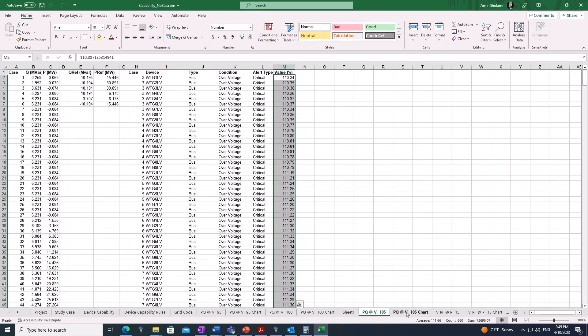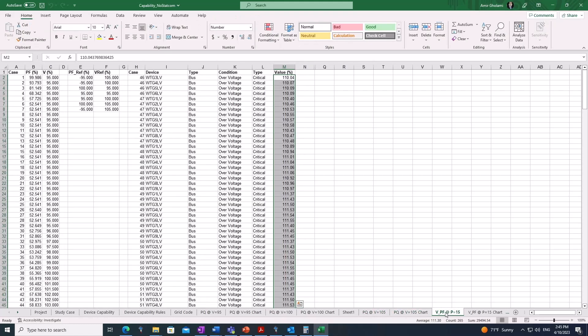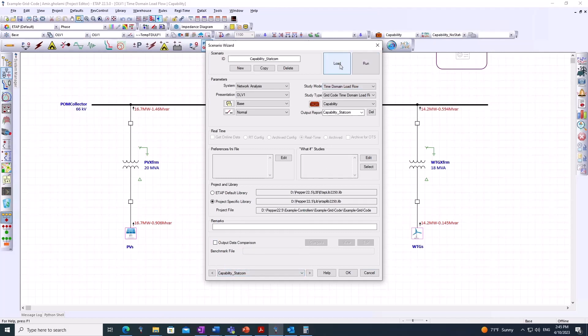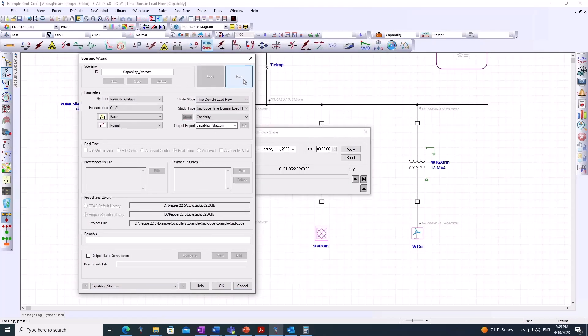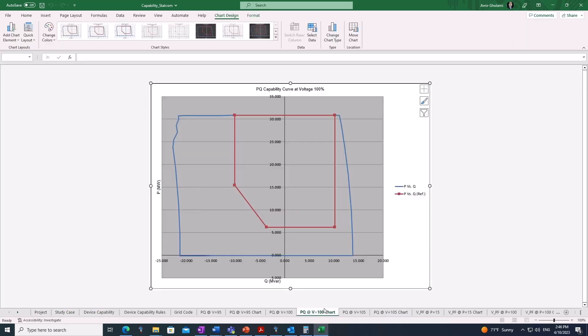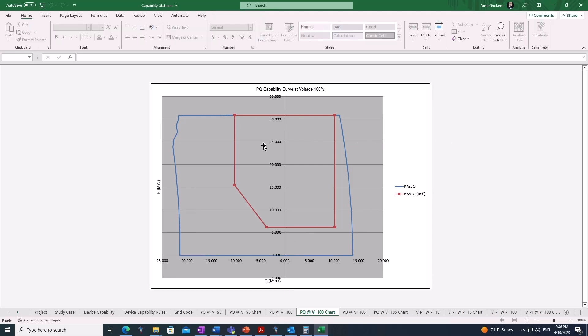In this case, at 100% voltage, the plant is not able to generate enough reactive power. Going into further sheets of the report, VQ and V power factor plots are shown at different active power levels — this is customizable, and the user can change it to V reactive power. To validate the impact of the STATCOM, we then run the 'capability with STATCOM' scenario, which puts the STATCOM in service. Going to the 100% voltage result, the blue curve now covers the red curve, meaning the reference is within the power plant capability — adding the STATCOM solves the issue.